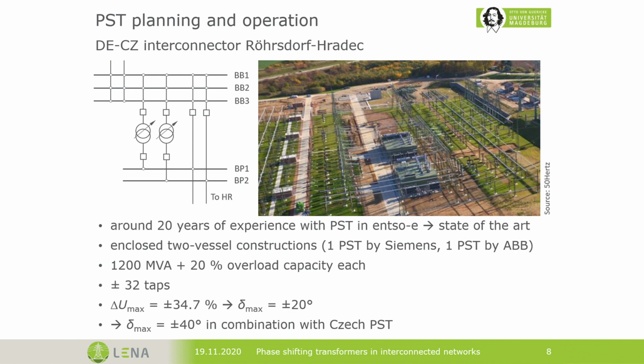So on this interconnector between Czech Republic and Germany, there are two PSTs in line. So it's a two-system interconnector, which means we have 4 PSTs installed on this interconnector. So in sum, on each line, we can have a maximum phase angle of 40 degrees.